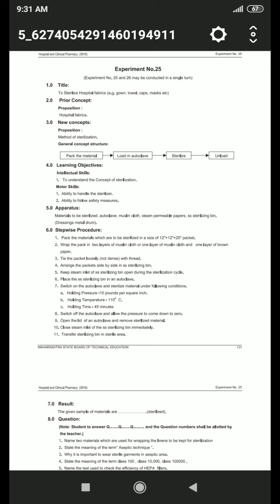Firstly, pack the material, and the size is 12 by 12 by 20 packets. Then wrap the pack in 2 layers of muslin cloth or 1 layer of brown paper. Then tie the pack loosely with thread. Then arrange the packets side by side in the sterilizing bin. Then keep the steam inlet of the SS sterilizing bin open during the sterilizing cycle. Then place the SS sterilizing bin in an autoclave. Then switch on the autoclave and sterilize the material under the following conditions: holding pressure, holding temperature and holding time.